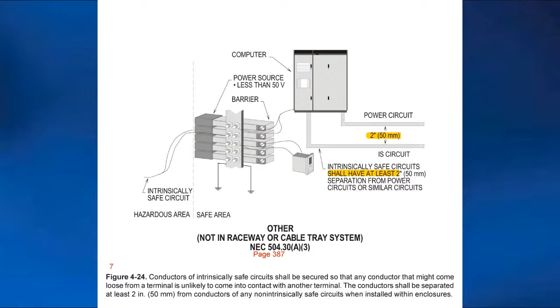And then, getting to your question, if you have a cable tray, raceway, or cable, that's where you put the label. And then for your terminals and your wiring, it's 504.80A and B. And then here's your seals, when you really need them and when they're required.